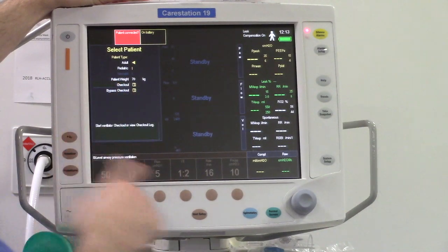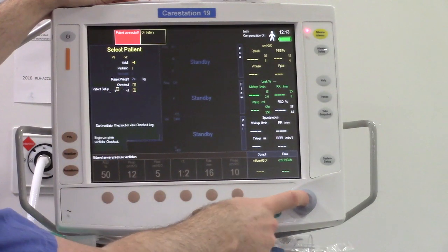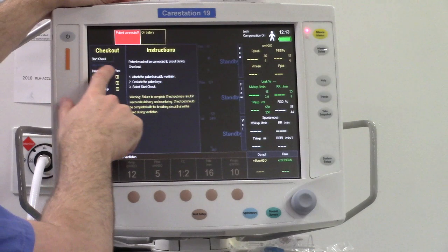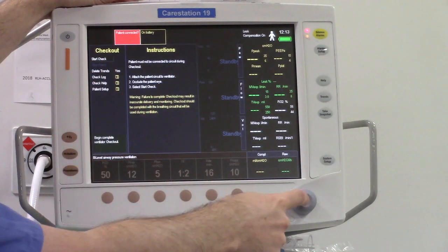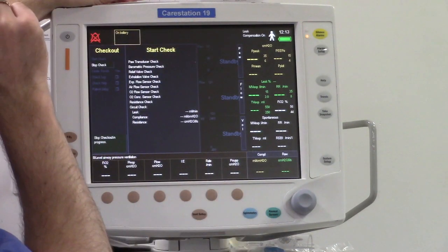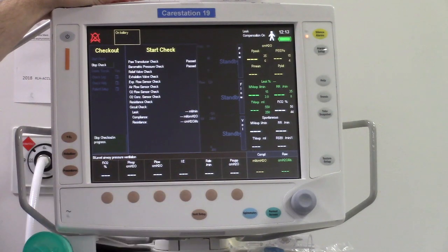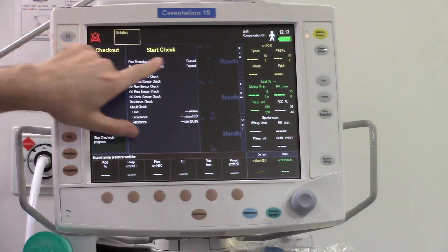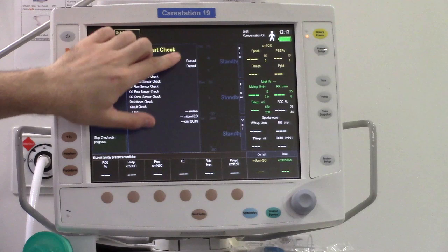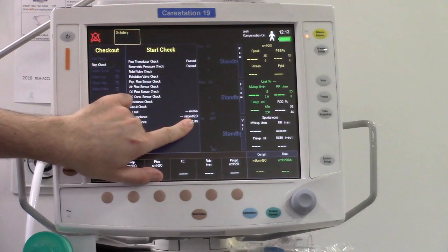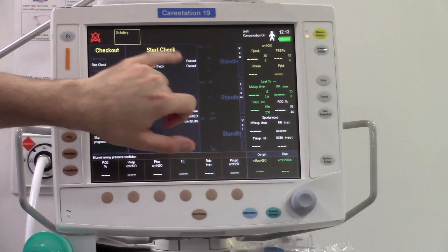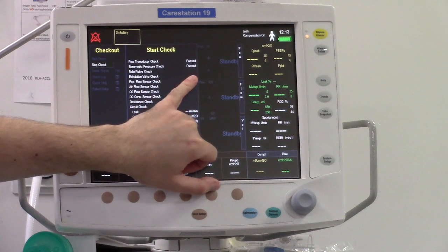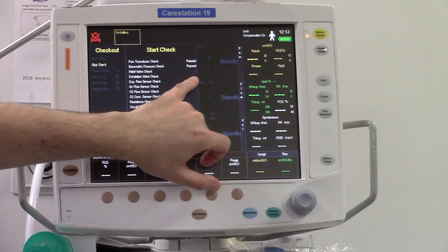As I said, it's already highlighted. You just need to press the knob down. Make sure start check is highlighted. You press again and it starts doing the check. You will go through all these steps and it will give us pass or fail. In the end, if you have at least one that has failed, it is not safe to use the ventilator.